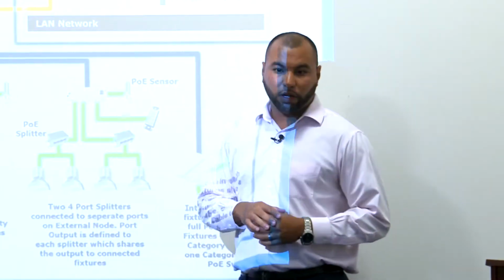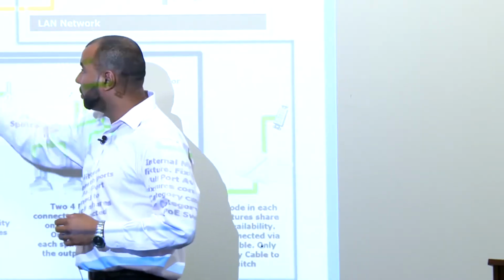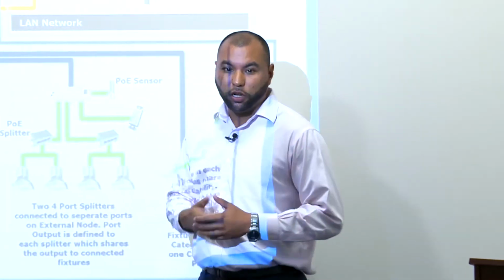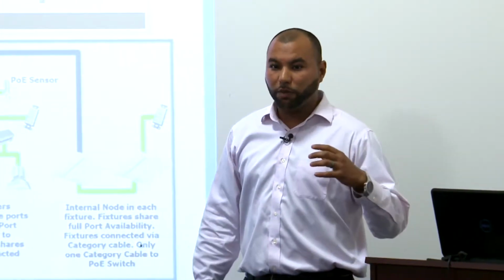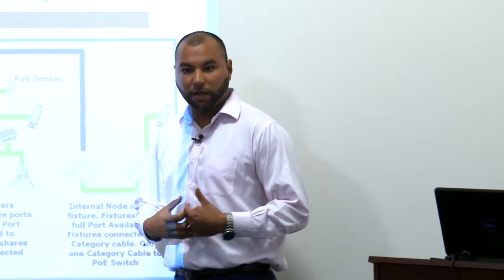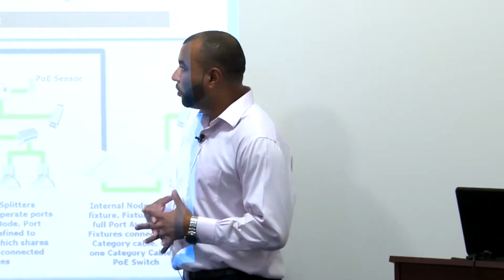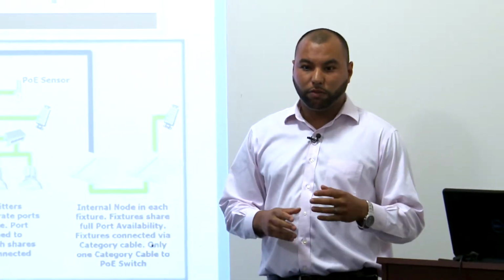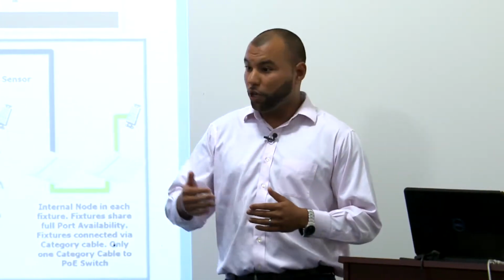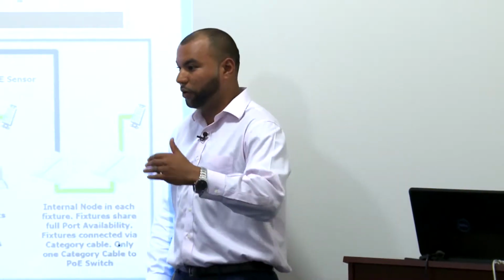The answer is you're limited by the power. Not all the lights are equal. You might have a light that's 20 watt. The limit is 48 watt inside the fixture. 60 watt comes out of the port, and 48 is what you can deliver. So when you're doing a job, or speccing and putting together a bill of materials, you always have to keep in mind how much power budget I have inside my device. I get this question a lot. Can I do 49? No, you can't. You're ETL certified to do 48. You can do anything below 48. You can't just do 49. You can't do 50.